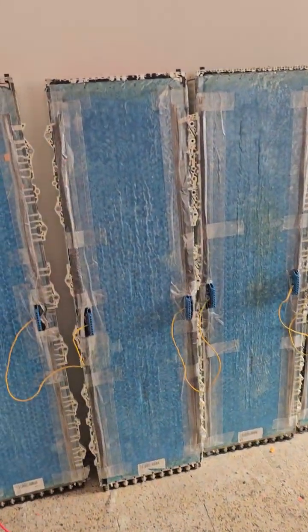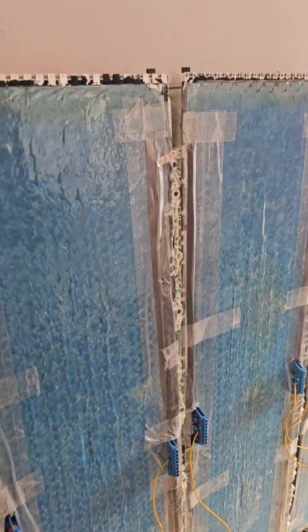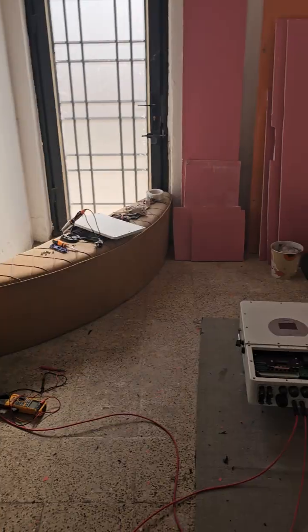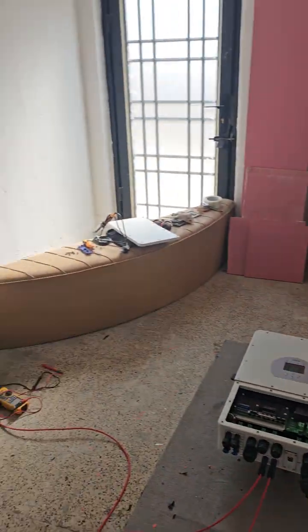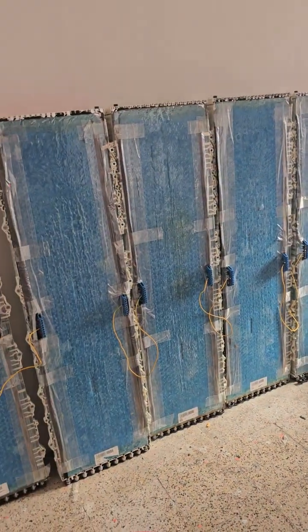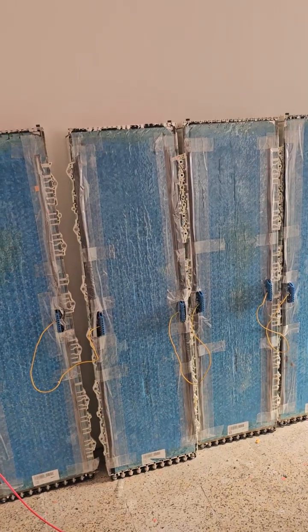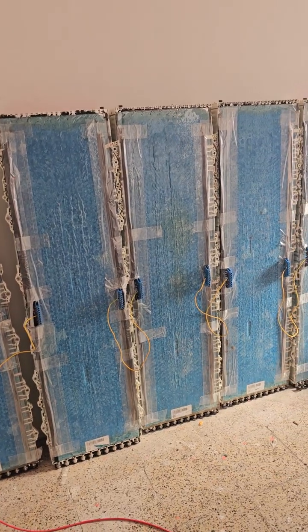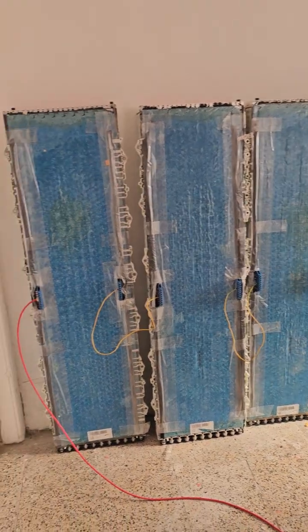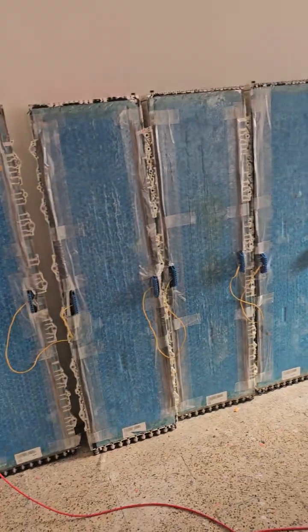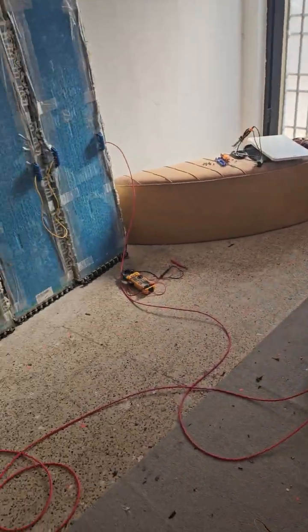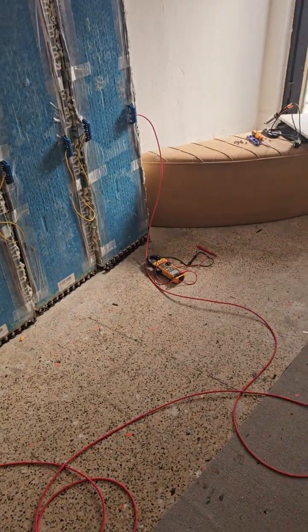Or some of them are using battery emulators to fake a specific CAN protocol to the inverter, telling it that it's connected to a brand specific battery so it will operate. I found another solution: there is no communication between these batteries and this inverter at all, and it's working normally.